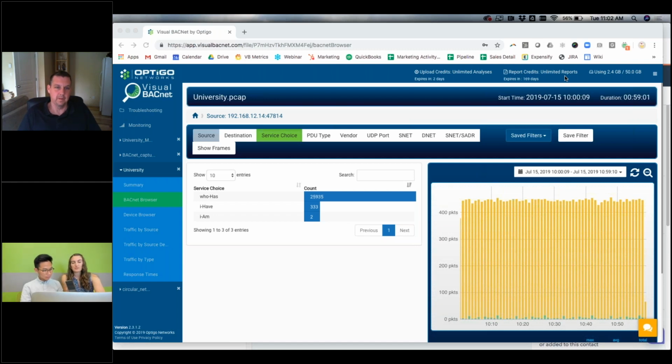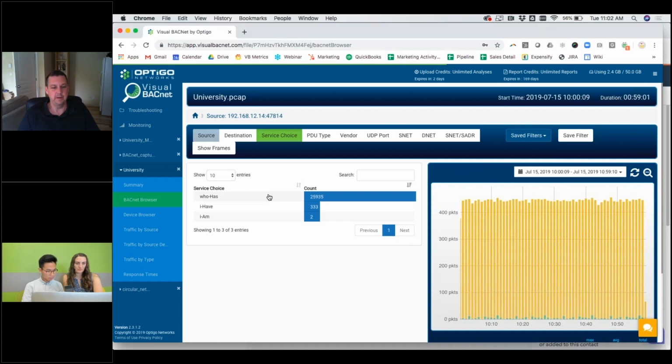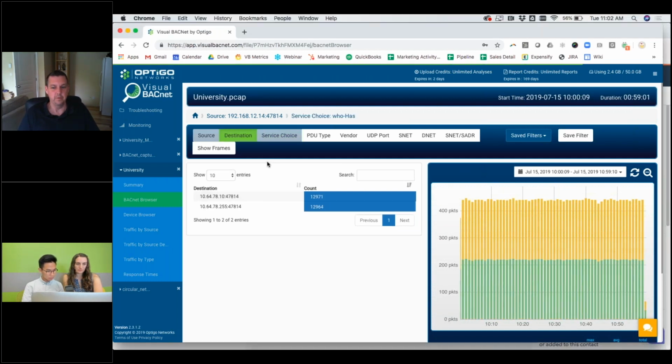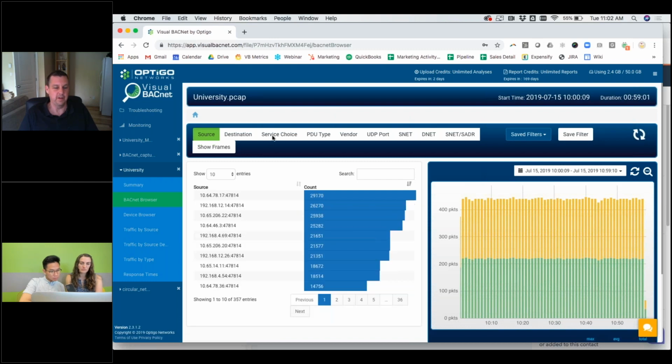So this becomes interesting when you have a who has. It goes from having an established data link, source and destination, and always getting the data, to the data link or the route to that network having disappeared or changed. Now you're asking, hey, where did it go? Who has this? I lost the information and it's no longer there. This can happen in a few different ways. It can happen if you're moving stuff around, if the site is being constructed and not fully done yet, or if network changes have been done but the controllers haven't been updated.